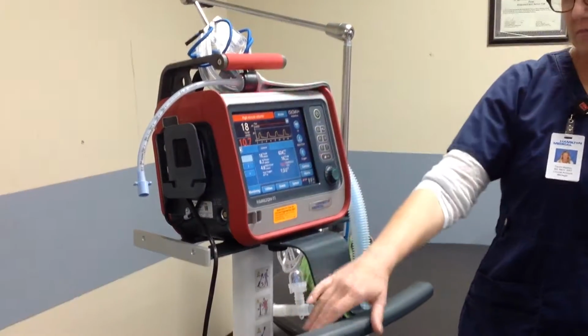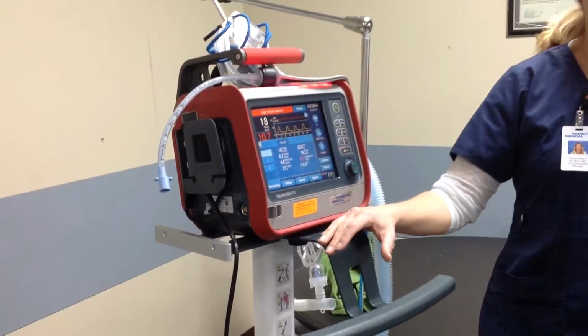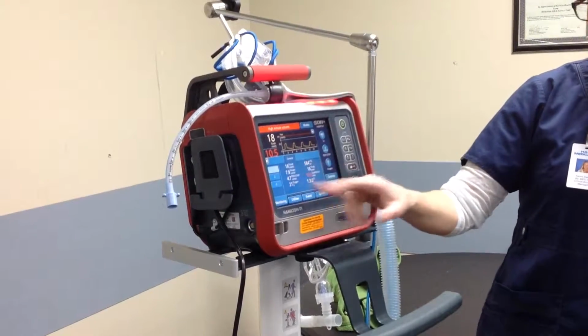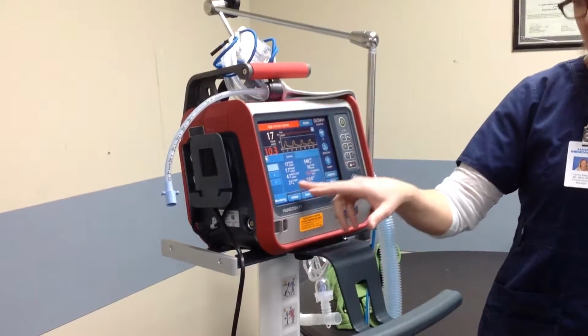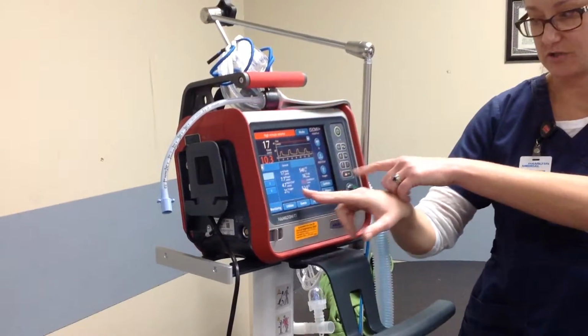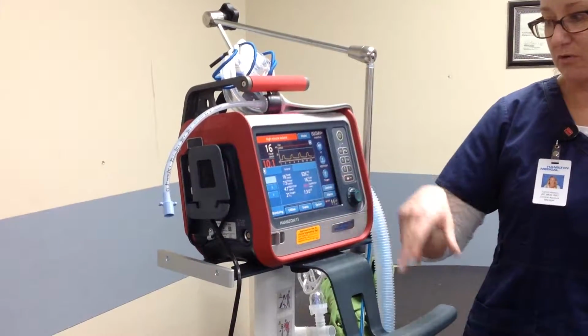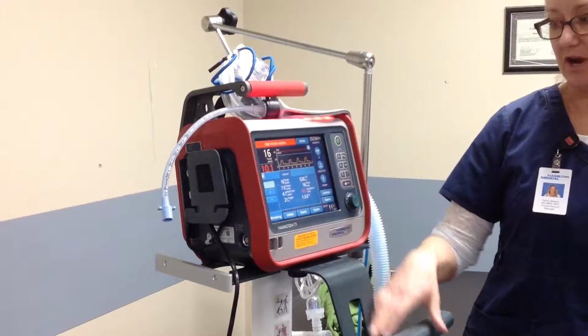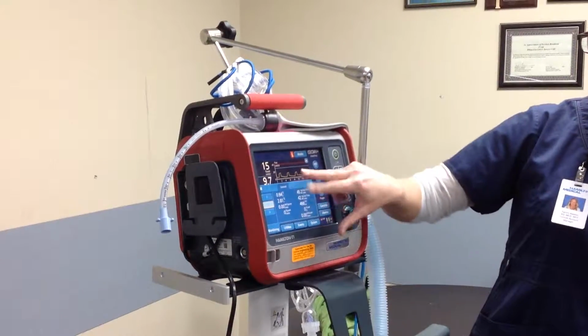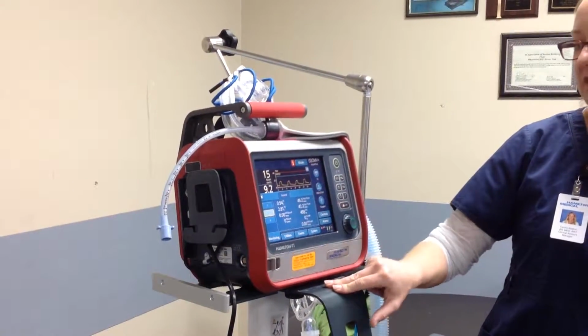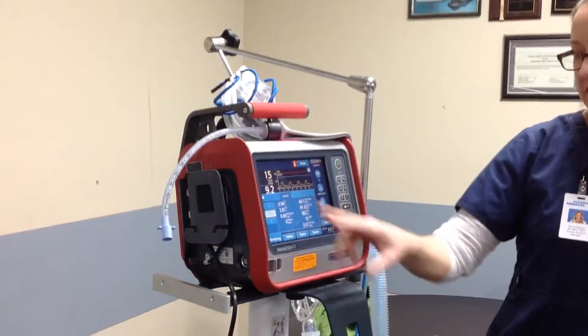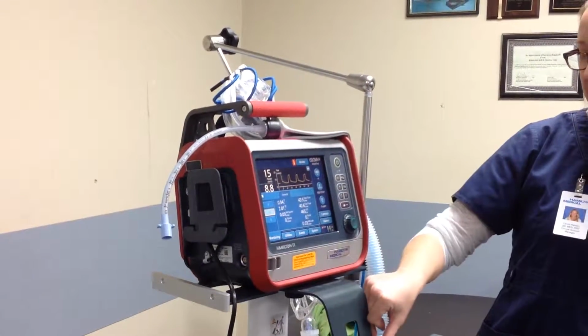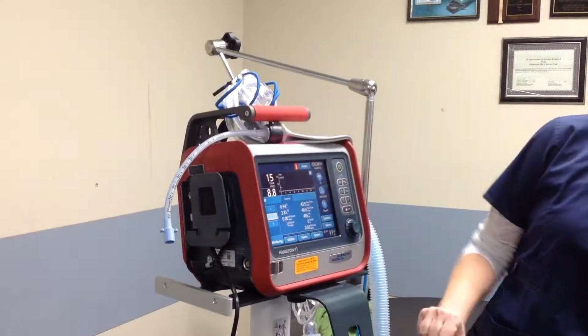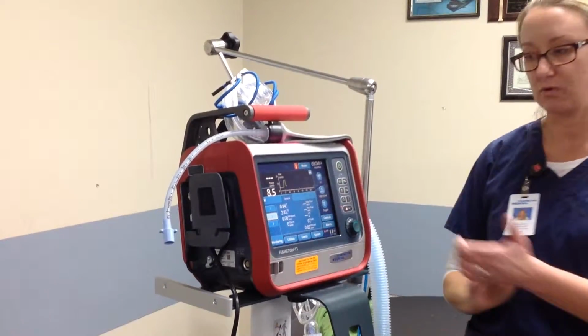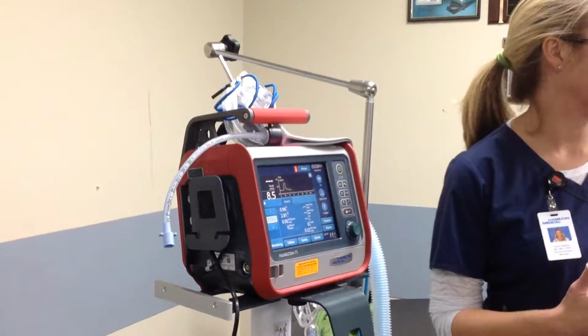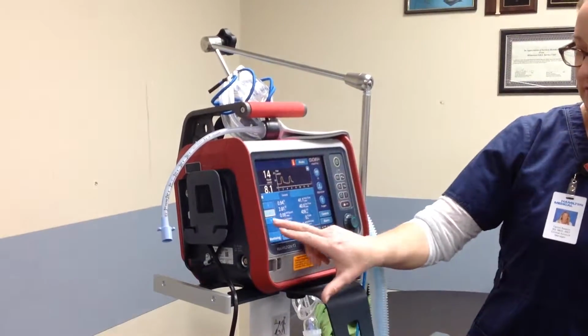Under the monitoring tab, that's where more information is. You have your peak pressures, your mean airway pressures, your PEEP, your analyzed oxygen versus your set oxygen, your exhaled tidal volume, your total rate, your minute ventilation, and your I to E ratio. On the second page, you have your I and your E times specifically. If this patient were breathing spontaneously, you get that information populated there. You get your inspiratory and your expiratory flow rates, and the difference between those two is what calculates your leak. So that information is there.